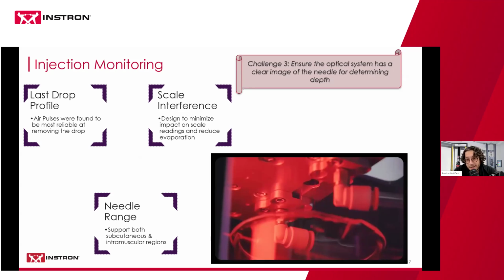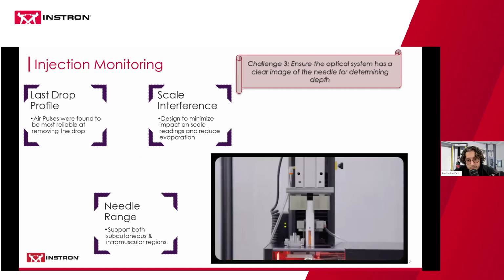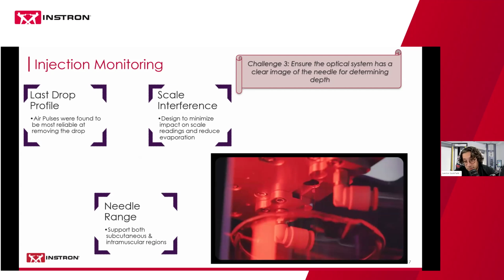Then we also had the consideration: how do we minimize that air current's effect on the scale? Minimizing how much of that air reaches the scale, because one, we don't want to impact the readings, and two, we want to minimize any evaporation of the fluid. The third consideration was how do we make sure this will work for needle lengths between 3 and 20 millimeters, to support both sub-Q and IM regions.